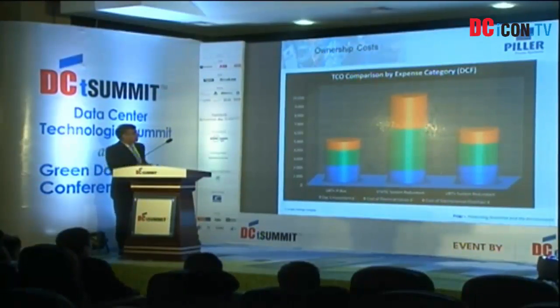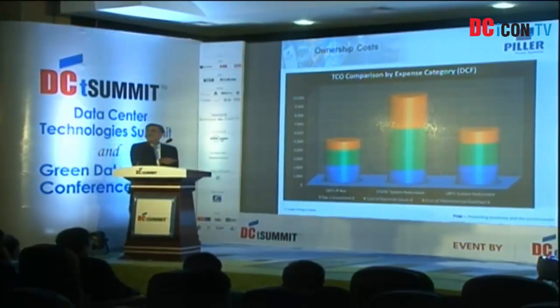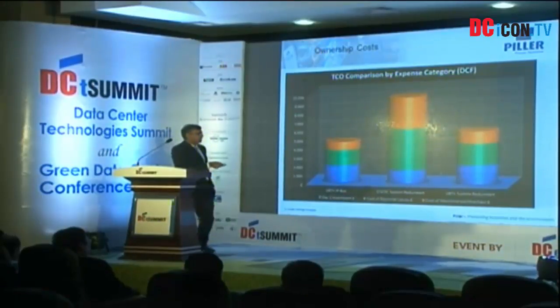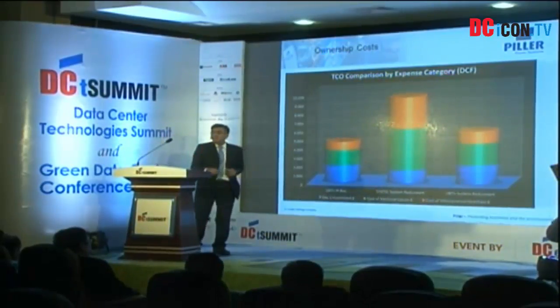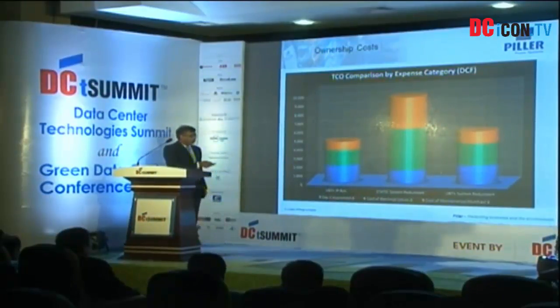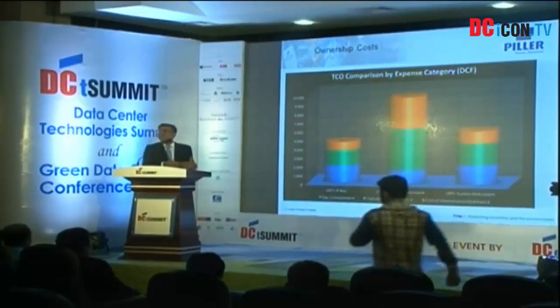This chart clearly says, this is a UBT rotary UPS with an IP bus system. This is a static system redundant system, and this is a UBT with a system redundant configuration. Three different configurations that we compare. First is the day one investment cost. Second, here the green color is the cost of electrical losses, and third is the cost of maintenance overhead. So you can compare this particular chart here. The ownership cost of a static system redundant is very high compared to a UBT system redundant, a similar configuration. And if you go to the other configuration, which is IP bus, it's much, much lower.